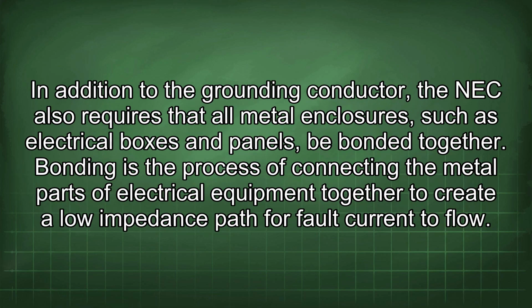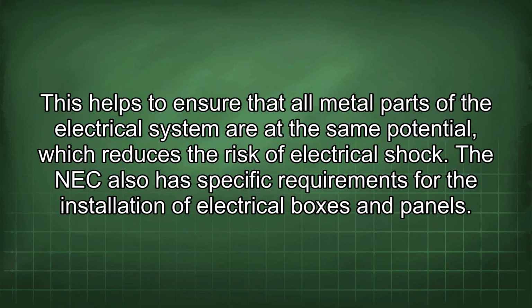In addition to the grounding conductor, the NEC also requires that all metal enclosures, such as electrical boxes and panels, be bonded together. Bonding is the process of connecting the metal parts of electrical equipment together to create a low impedance path for fault current to flow. This helps to ensure that all metal parts of the electrical system are at the same potential, which reduces the risk of electrical shock. The NEC also has specific requirements for the installation of electrical boxes and panels.